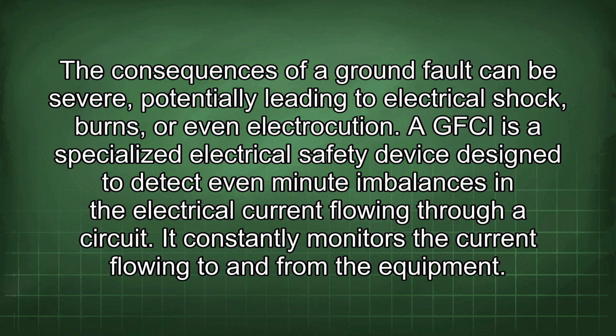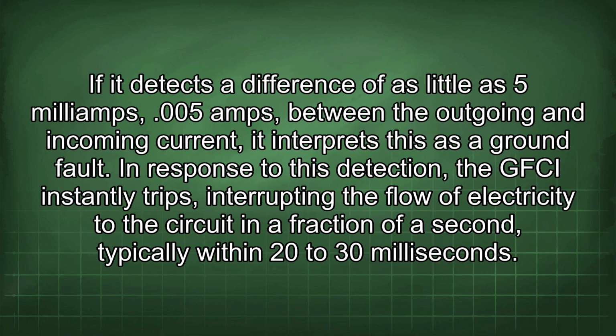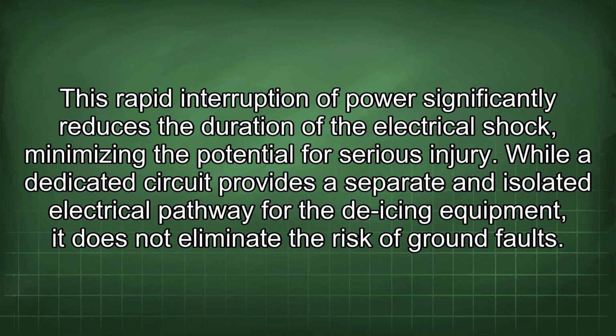A GFCI is a specialized electrical safety device designed to detect even minute imbalances in the electrical current flowing through a circuit. It constantly monitors the current flowing to and from the equipment. If it detects a difference of as little as 5 milliamps between the outgoing and incoming current, it interprets this as a ground fault. In response, the GFCI instantly trips, interrupting the flow of electricity to the circuit in a fraction of a second, typically within 20 to 30 milliseconds. This rapid interruption of power significantly reduces the duration of the electrical shock, minimizing the potential for serious injury.